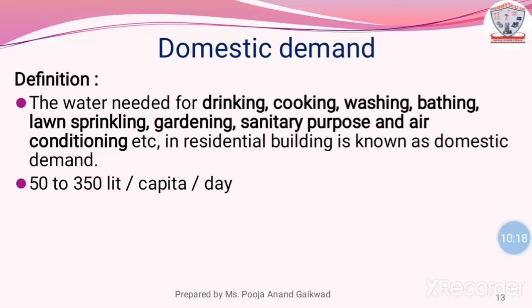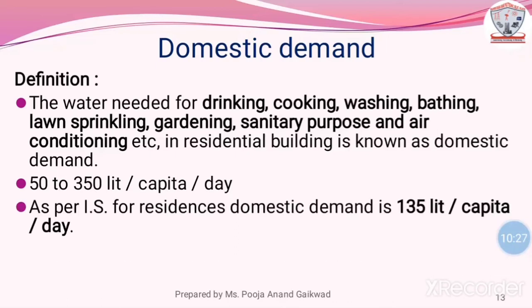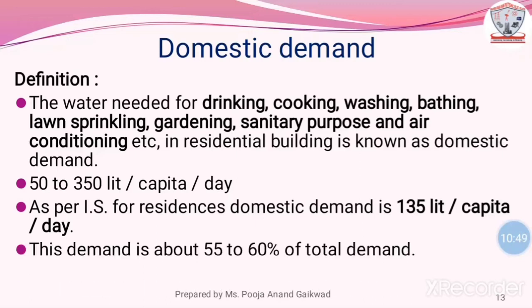The demand may lie between 50 to 350 liters per capita per day. The demand depends upon habits, living conditions, and standards of people. As per IS standards, that is Indian standards for residences, the domestic demand is about 135 liters per capita per day.